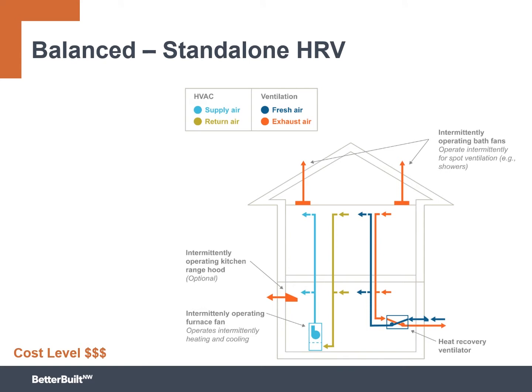Next up, we have the standalone HRV, or the dedicated heat recovery ventilator. Now, to many people, this is what we think of, again, when we hear the words balanced ventilation. And the use of heat recovery or energy recovery is a pretty decent option because now, again, we're doing this without taking that big energy penalty. With these systems, the incoming air has a percentage of the outgoing air's heat recovered and transferred to it. So this might mean when we're exhausting 70-degree air and bringing in 30-degree air, we might be able to get that incoming temperature at least up to the low 60s, which is a whole lot better than 30-degree, 40-degree, or even 50-degree air blowing on grandma's head.